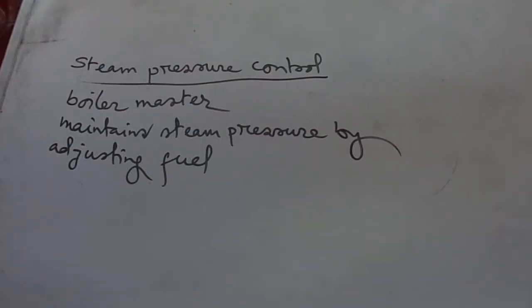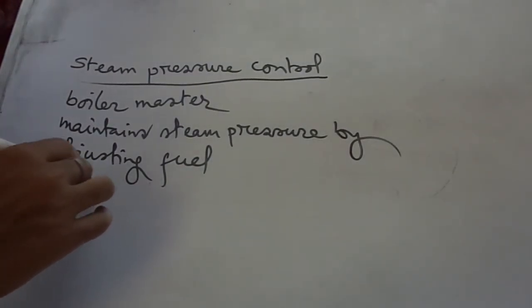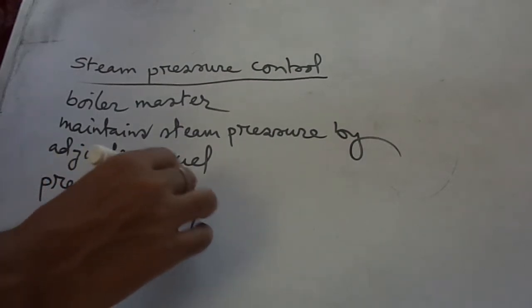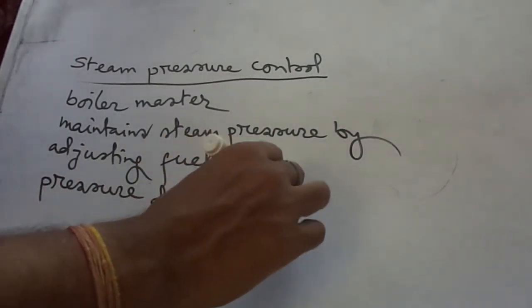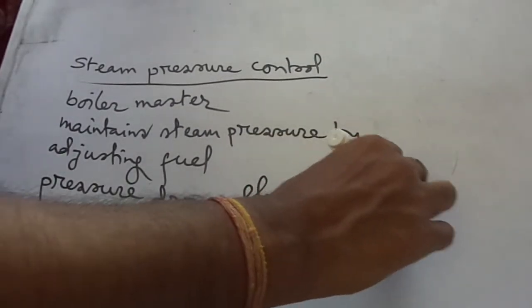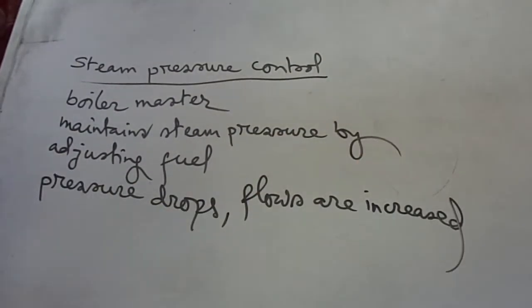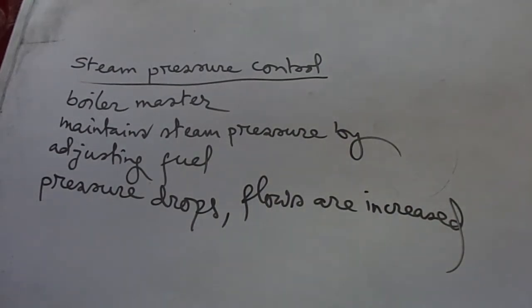When pressure drops, the flows are increased. The steam pressure sensor acts directly on the fuel flow and airflow control, such as the pulverized coal power drives and forced draft fan, to effect the desired changes. A trimming signal from fuel flow and airflow sensors maintains the proper fuel air ratio.